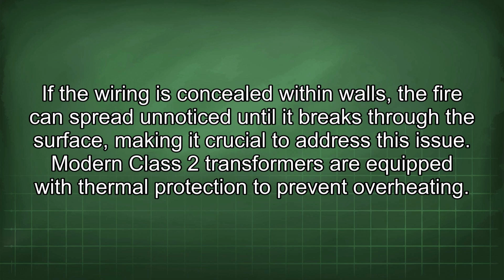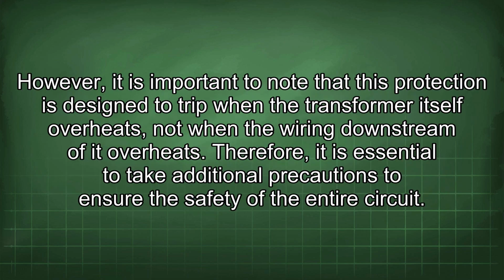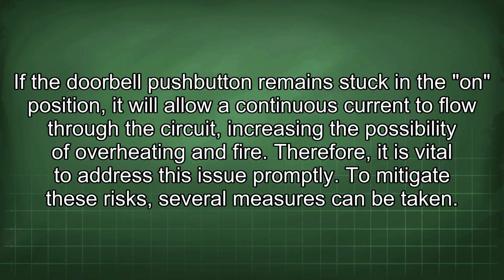Modern Class II transformers are equipped with thermal protection to prevent overheating. However, it is important to note that this protection is designed to trip when the transformer itself overheats, not when the wiring downstream of it overheats. Therefore, it is essential to take additional precautions to ensure the safety of the entire circuit. If the doorbell push button remains stuck in the on position, it will allow a continuous current to flow through the circuit, increasing the possibility of overheating and fire. Therefore, it is vital to address this issue promptly.